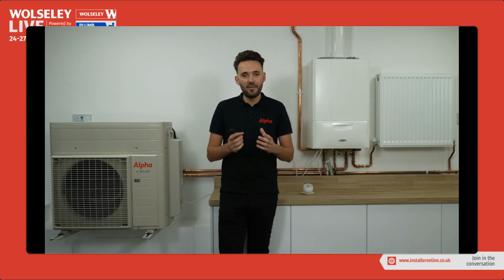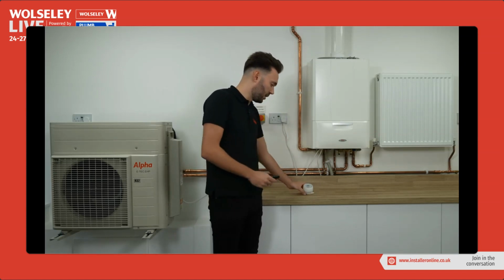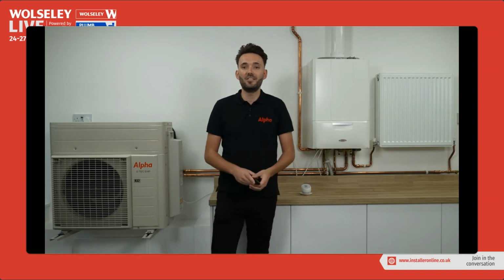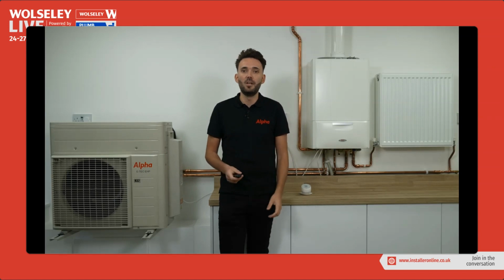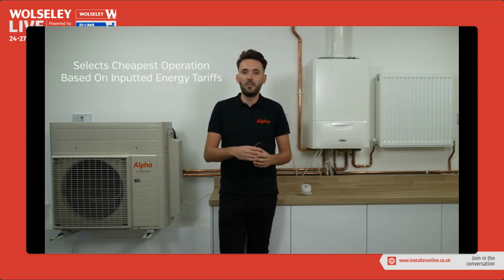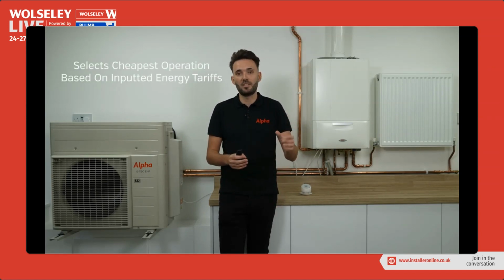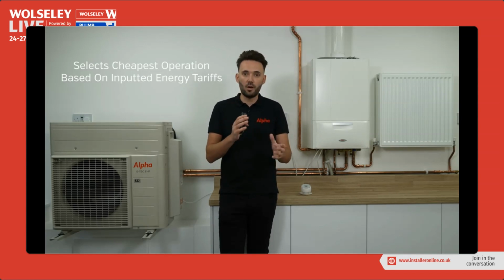Now, how it works is very clever, and this is where our smart tech controller comes in. When the engineer's finished installing the system and goes through the commissioning stages, he'll input the electricity price per kilowatt and the gas price per kilowatt you pay, from a recent energy bill. Then, every time there's a call for heat, or we turn our thermostat up, the smart tech will do a quick cost calculation.